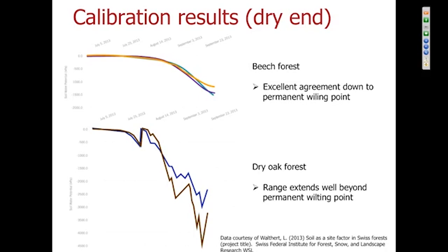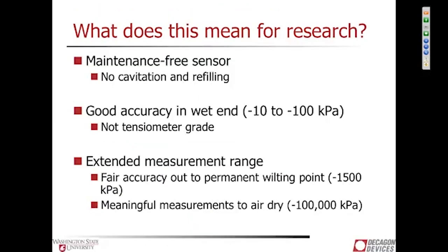So as you go drier, you get further from where we've done most of the calibration, and we try not to put error bars on that because we're a little bit uncertain of how the calibration should hold there. We do use a scientifically defensible calibration procedure in that dry range, and so we expect that the accuracy should be pretty good, but it's really hard to put error bars on that, and we're working on that presently, trying to figure out just how accurate we are as we get all the way down to air dry.